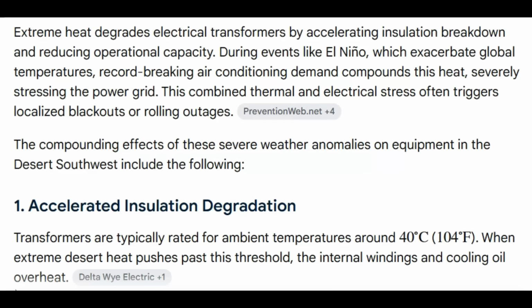The compounding effects of these severe weather anomalies on equipment in the desert Southwest include the following. Accelerated insulation degradation. Transformers are typically rated for ambient temperatures of up to 104 degrees Fahrenheit, or 40 C. When extreme desert heat pushes past this threshold, the internal windings and cooling oil overheat. Again, we've been through that.